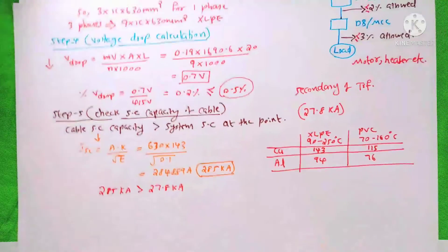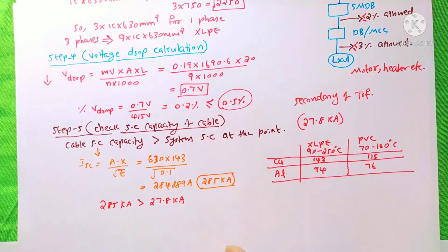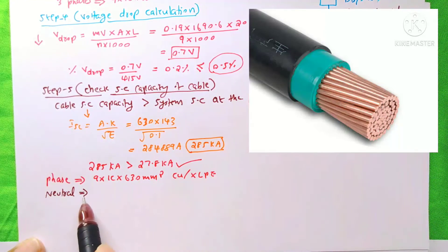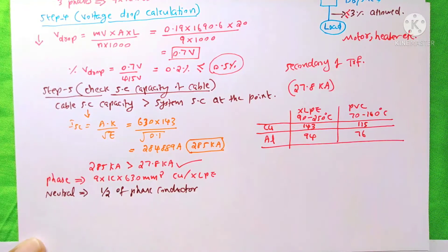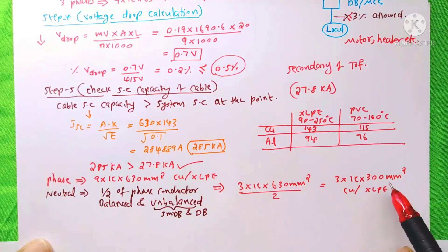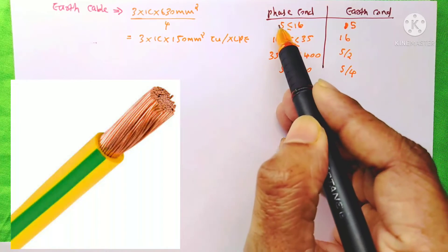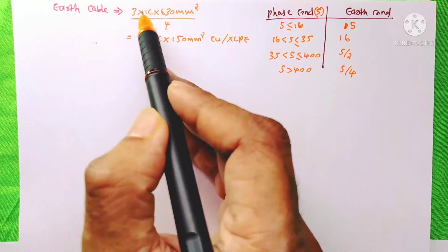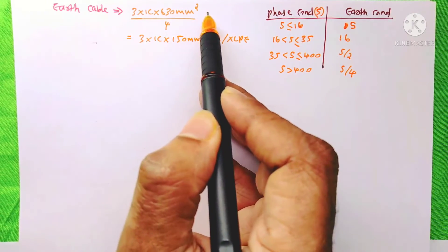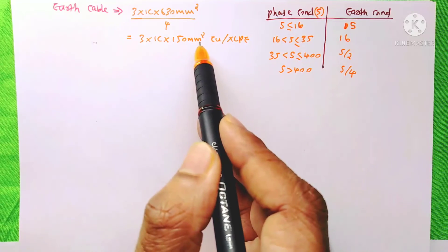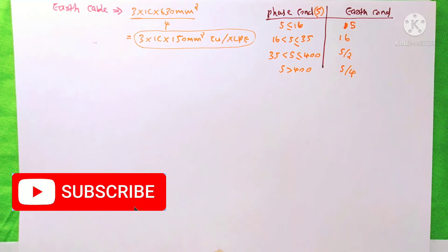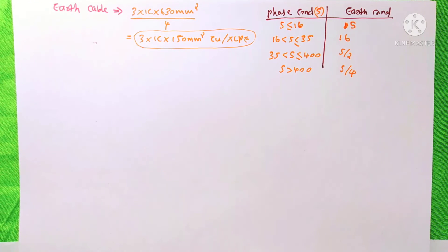Therefore, 9 runs of 1-core 630 mm² XLPE copper cable are suitable for our system. For the neutral cable of the MDB, we use half the phase conductor: 3 × 1-core 300 mm² copper XLPE. For the earth cable, since 630 mm² > 400 mm², the earth conductor is 3 × 1-core 150 mm² copper XLPE cable. Please subscribe to the YouTube channel. Thanks for watching.